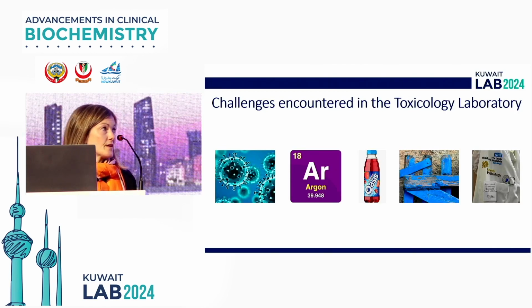So the gas delivery to our hospital has failed 3 times over the past 12 months. So it is really important that we monitor how much argon we've got left, and when we're getting down to critical values, that we don't run the routine analysis, we don't run the nutritional copper, zinc, selenium measurement. We wait until we've got a delivery so that we know if an urgent blood lead or mercury request comes in, that we can deal with that request.